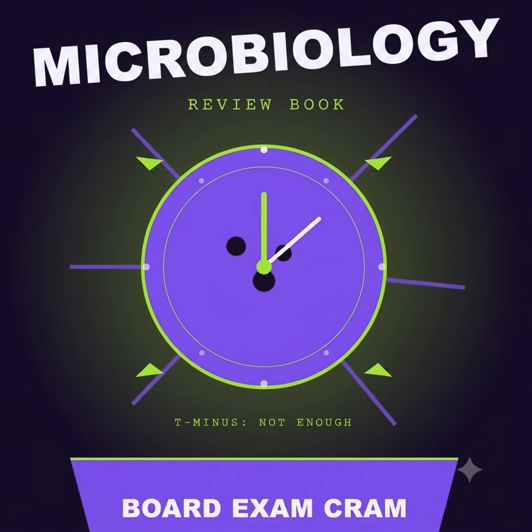Let's do it. First up, autoclave specifications. 15 psi, 121 degrees Celsius for 15 minutes. The boards love this because sterilization is a life or death absolute in the hospital. If you don't know the exact physical parameters to achieve the destruction of endospores, you are dangerous in a laboratory setting.